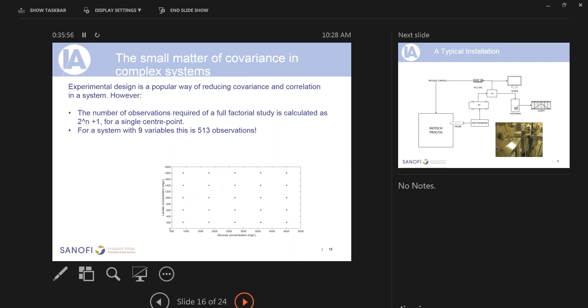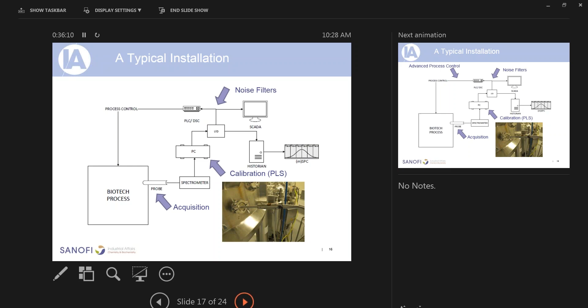But the graph below shows you how we broke down the correlations between the variables. Here we have glucose and lactate, and you can tell that each of the measurements in our calibration curve is uniquely resolved from all the others, and you couldn't plot a line through there and get an R squared greater than 0. There's no covariance in our system, and you could do this for any combination of variables, and the R squared would be 0, which from our perspective means that there's no covariance. And if we are capable of building a calibration, we must be measuring the compounds uniquely. Okay, next slide, please.